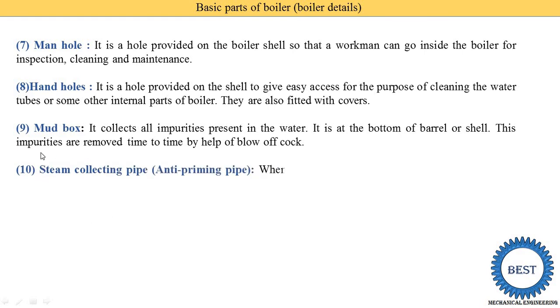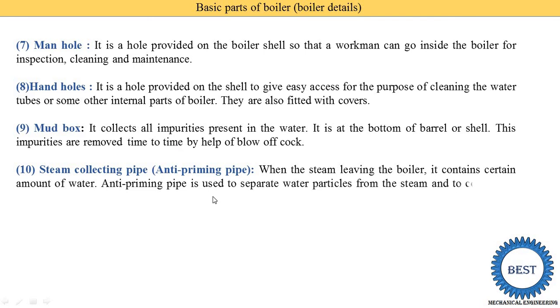The next part is the steam collecting pipe, also known as the anti-priming pipe. Steam is generally collected in the upper part of the shell. When steam leaves the boiler, it contains a certain amount of water, which is known as wet steam. The anti-priming pipe is used to separate the water particles from the steam and collect only dry steam from the boiler, which is then supplied wherever it is required.